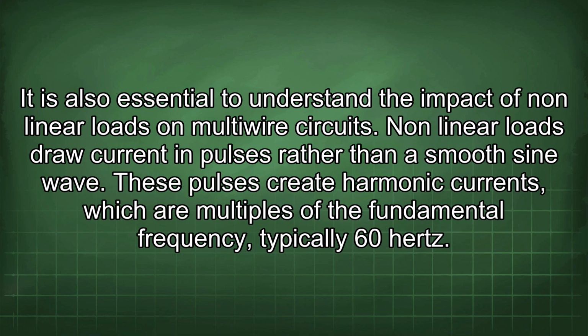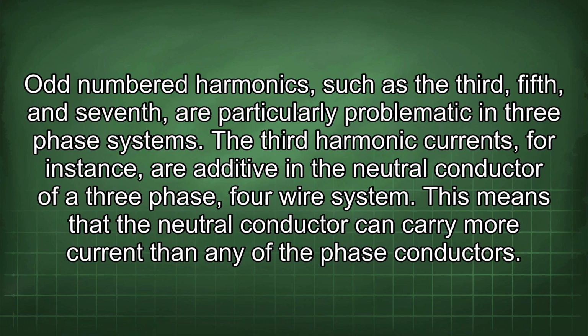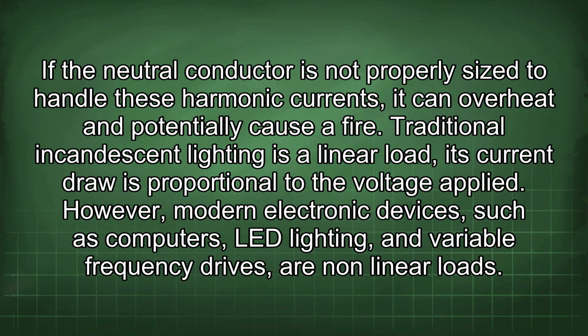It is also essential to understand the impact of nonlinear loads on multi-wire circuits. Nonlinear loads draw current in pulses rather than a smooth sine wave. These pulses create harmonic currents, which are multiples of the fundamental frequency, typically 60 Hz. Odd-number harmonics, such as the third, fifth, and seventh, are particularly problematic in three-phase systems. The third harmonic currents, for instance, are additive in the neutral conductor of a three-phase, four-wire system. This means that the neutral conductor can carry more current than any of the phase conductors. If the neutral conductor is not properly sized to handle these harmonic currents, it can overheat and potentially cause a fire.